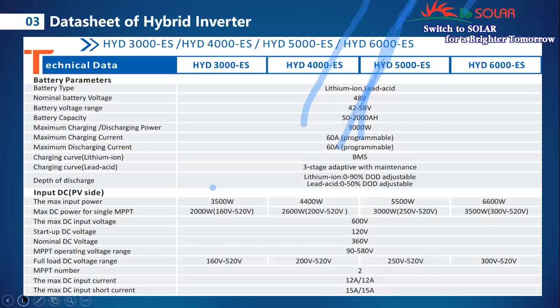The main thing is the depth of discharge: for lithium ion batteries it is 90%, and for lead acid batteries it's 0 to 50% adjustable. I will explain what the depth of discharge is for hybrid inverters in terms of the battery. DOD means depth of discharge, or how much energy the battery has delivered. For example, if the battery is 100% charged, it means it has 0% DOD. If the battery is 70% charged, it means 30% DOD. And if the battery is 100% empty, it means 100% DOD. It means it will deliver 100% of the energy to the load to drive the load, right?